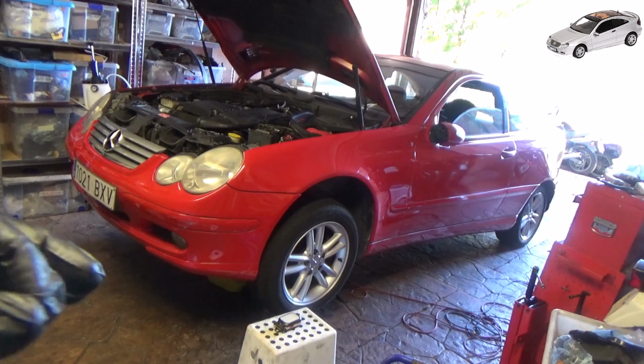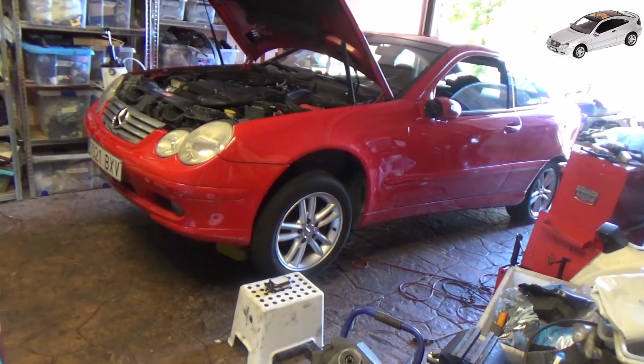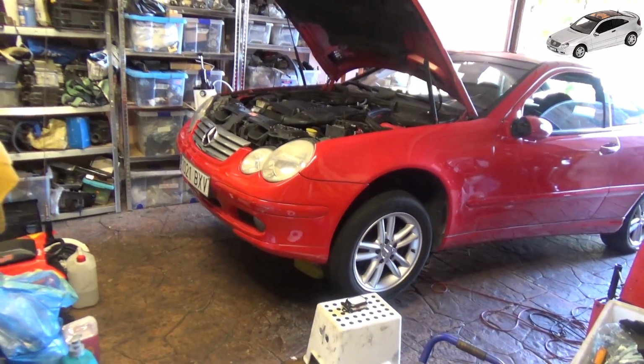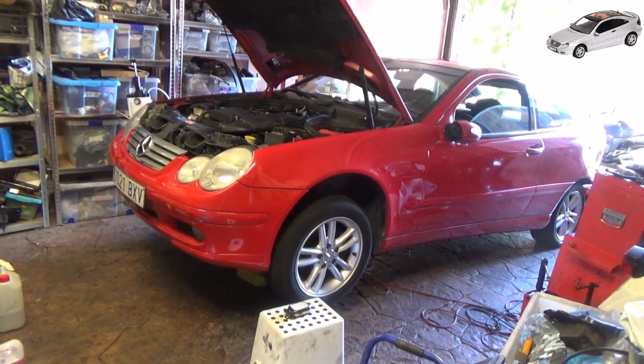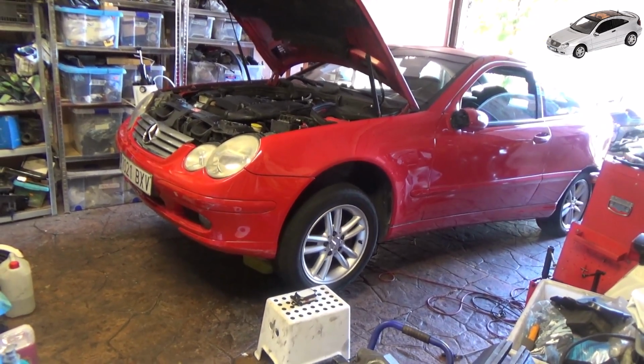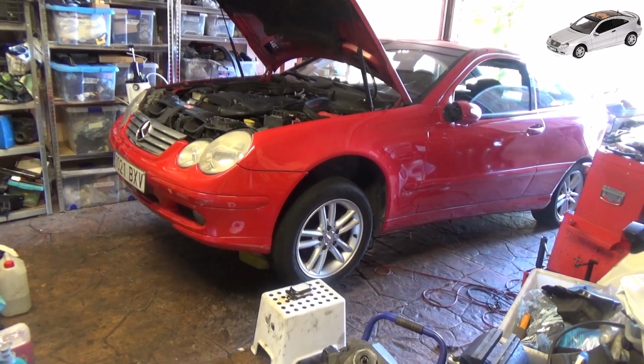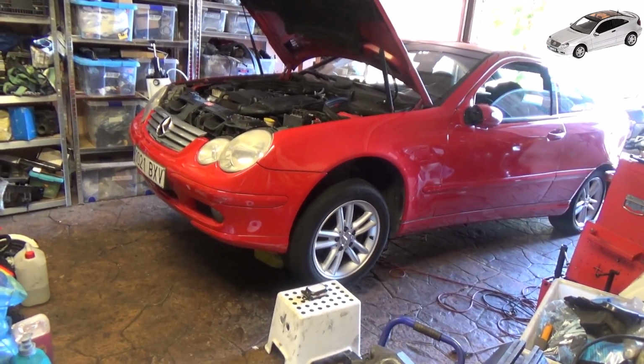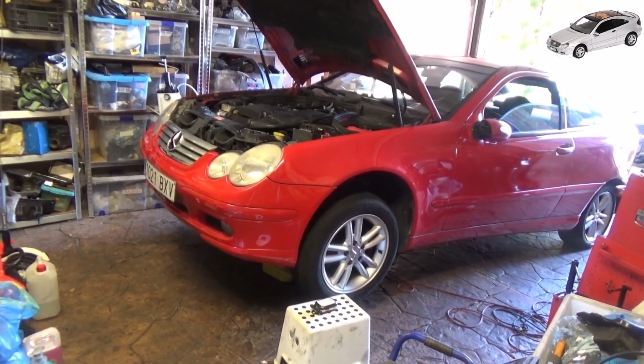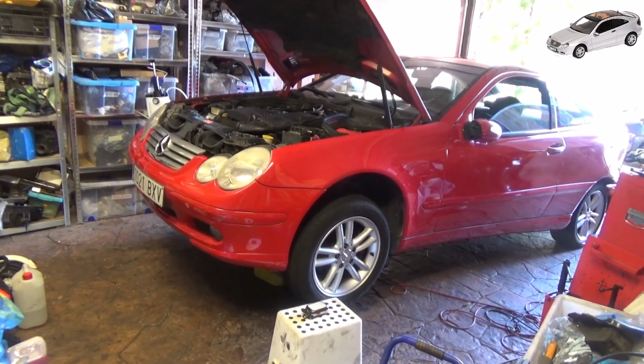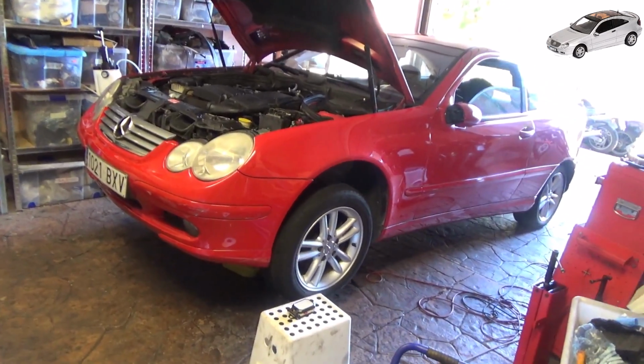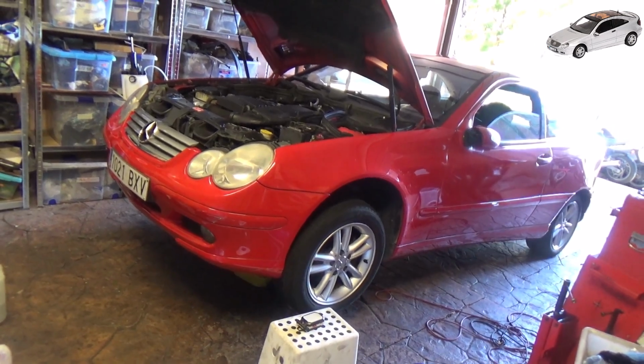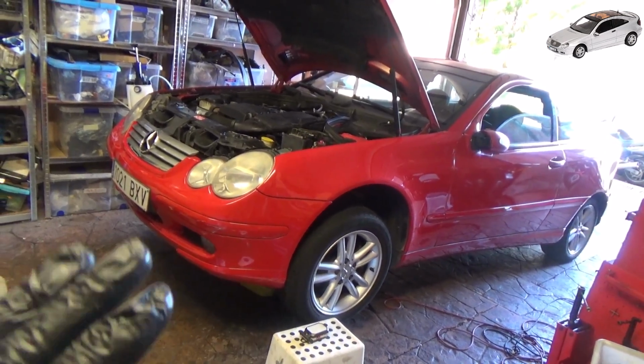So, from less problematic to more problematic, the question is the following. In the best case scenario, there's a fault in the oil cooler or heat exchanger. It's said that when there's a crack or some internal leak in the oil cooler, it causes the oil to mix, and the seals may be bad and it leaks. But first we have to see where it leaks.